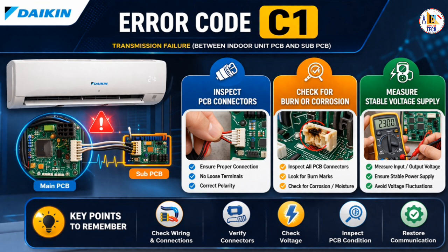Step 3. Connector and voltage check. After verifying the wiring, examine the PCB connectors closely. Look for signs of burns, corrosion, or any other physical damage that may interfere with communication signals. It's also crucial to measure the voltage supply to the PCBs. Fluctuations or unstable voltage can cause the system to miscommunicate, leading to recurring C1 errors. Ensuring stable voltage and clean, undamaged connectors helps maintain reliable communication between the main and sub PCBs.